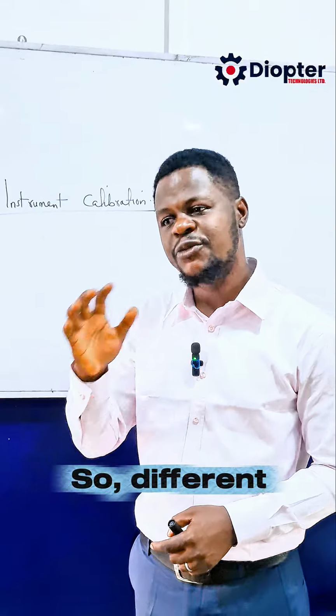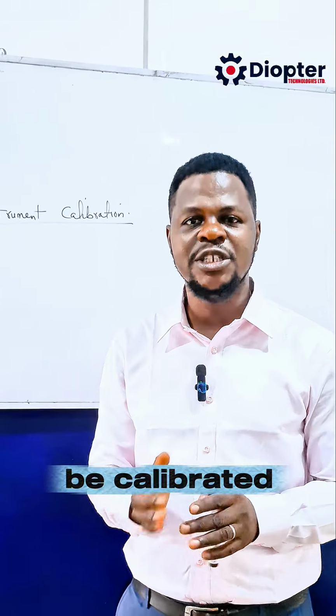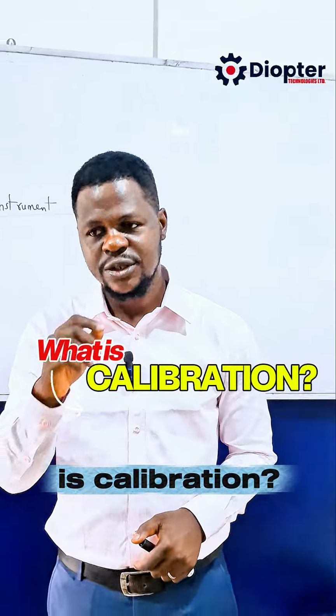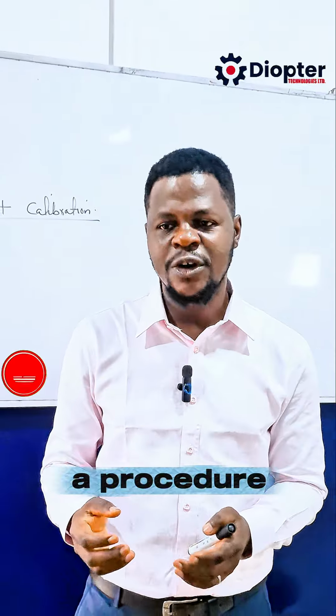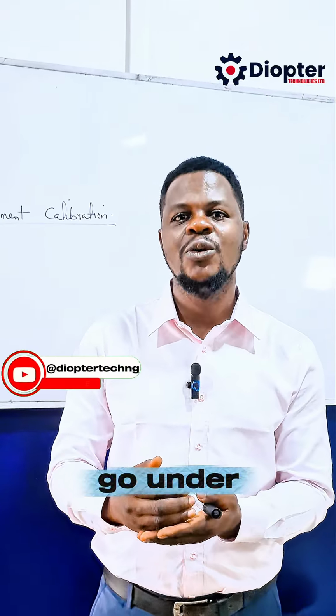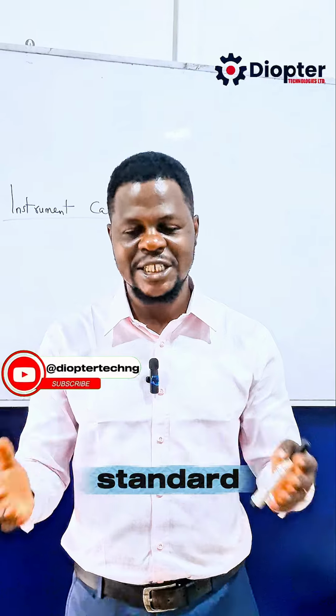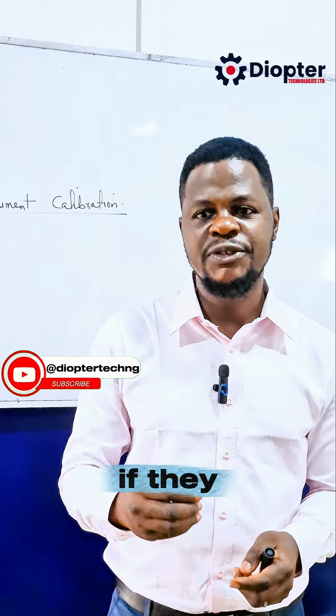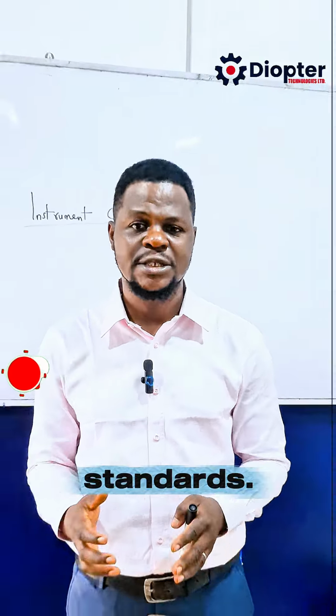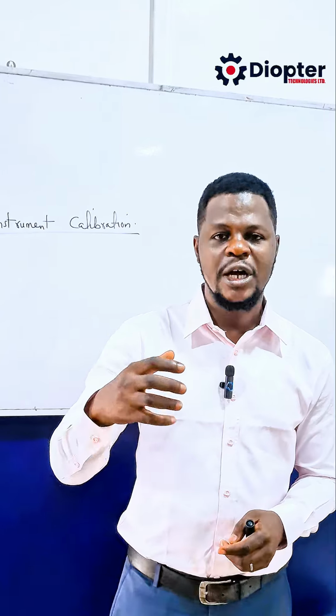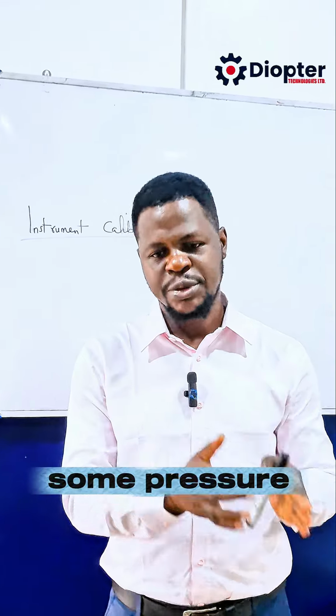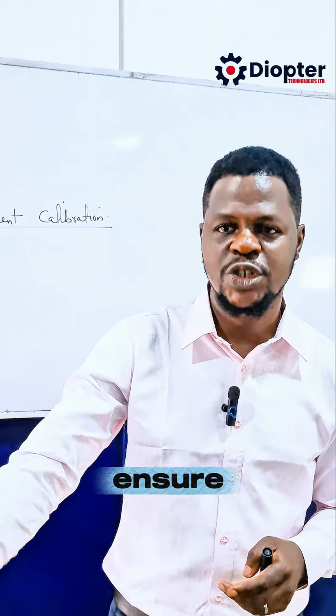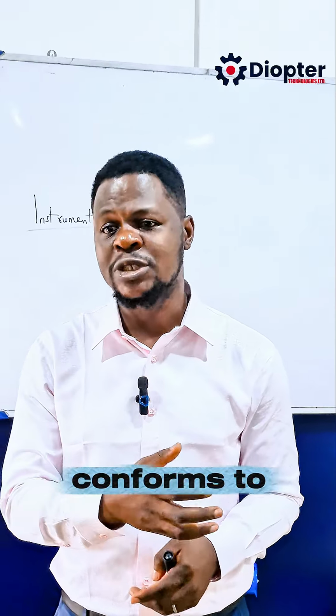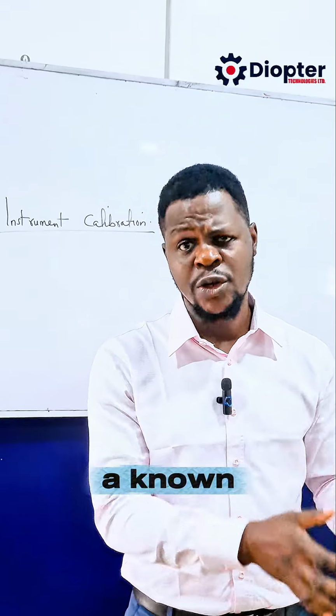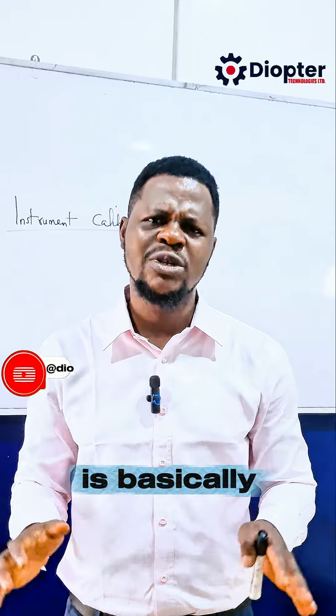Okay, so different instruments can be calibrated differently. So what is calibration? Calibration is a procedure of making instruments go under a particular standard to check if they conform to standards. For example, a pressure transmitter is actually subjected to some pressure signals to ensure that it conforms to standard after comparing it with a known standard. So that is basically what calibration is all about.